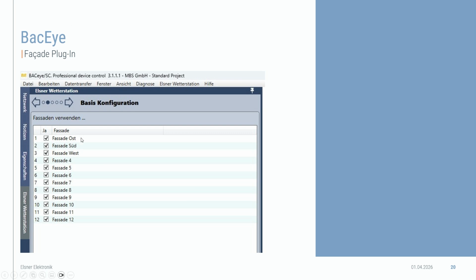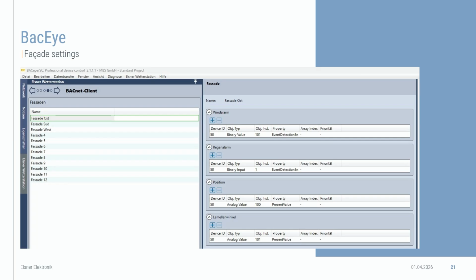So you can deactivate or activate the individual facades, and here you can even set individual parameters and logic like you would expect from a KNX ETS application. This makes the system even more powerful. It's not just detecting the device via the BACnet browser and identifying the objects, it even provides a plug-in with the logic to control facades.